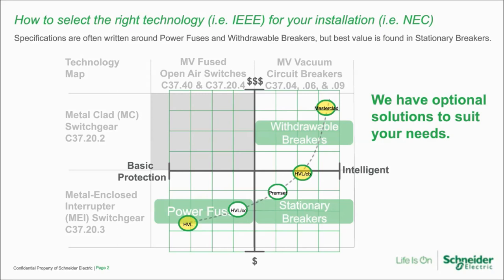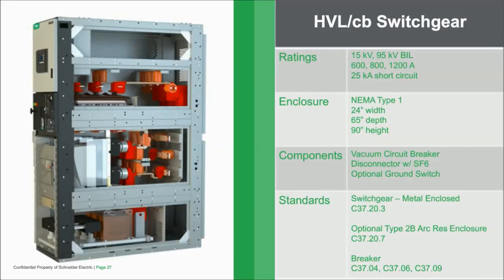Does the entire HVLCB lineup have to be de-energized prior to disconnecting a single breaker compartment? This is always a point of confusion — the answer is no. Each and every single section has its own disconnect. The main bus passes through several different feeders. In fact, we can connect HVLCB and HVLCC feeders together in a lineup, each one with its own disconnect.